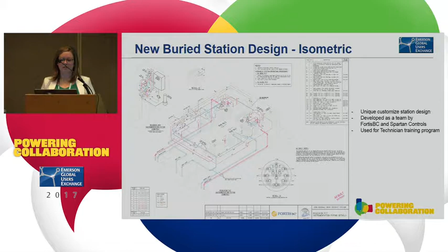They also incorporated a little orifice plate into the set for a bit of information on what the flow is actually doing at that station. In the old days they used pressure recorder charts that technicians would pick up and bring back, and the engineering group would review them long term to figure out how to move forward. They also put both the instrumentation and piping lines on the P&ID so they could tell how everything worked out.